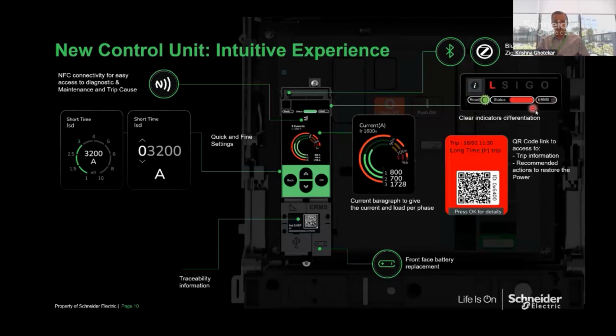Another new feature which we are bringing to the market is ERMS, Energy Reduction Maintenance Setting. This is mainly for the end users, for an operator who is working there. So in case there is an arc flash in the panel, and there is an operator working in the electrical room, and this ERMS is activated, the breaker will instantly get into the tripping zone, and it will trip instantly, whatever is the setting done to the breaker. So we will discuss this ERMS also.